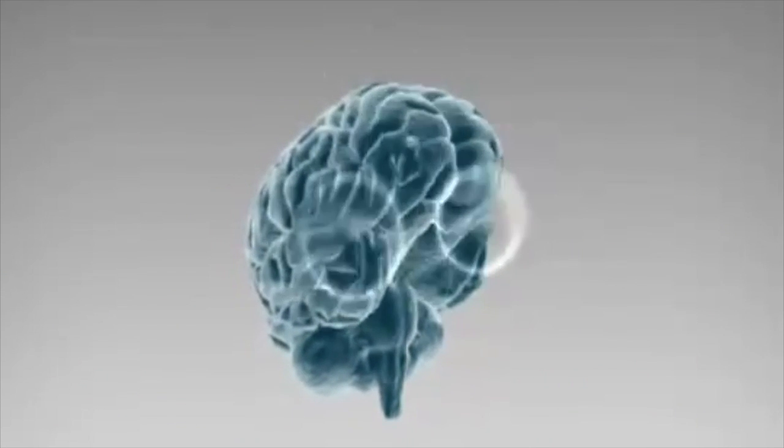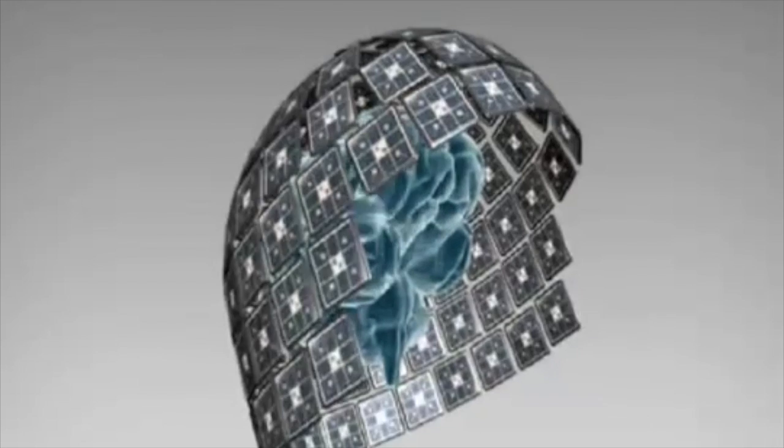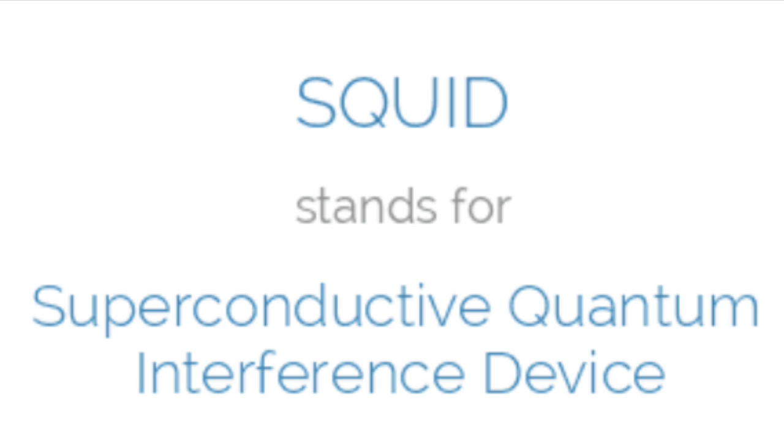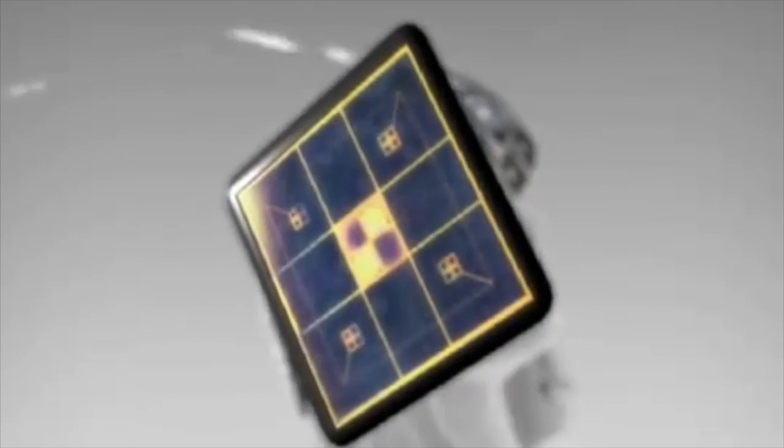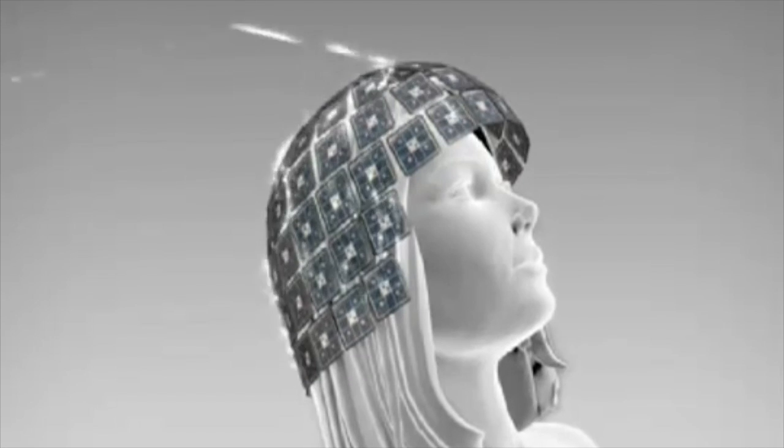This magnetic field which is produced is extremely small, yet magnetoencephalography is able to pick it up with the use of a device called SQUID, which stands for Superconducting Quantum Interference Device. SQUIDs are sensors which are bathed in a helium cooling unit to approximately negative 269 degrees Celsius.